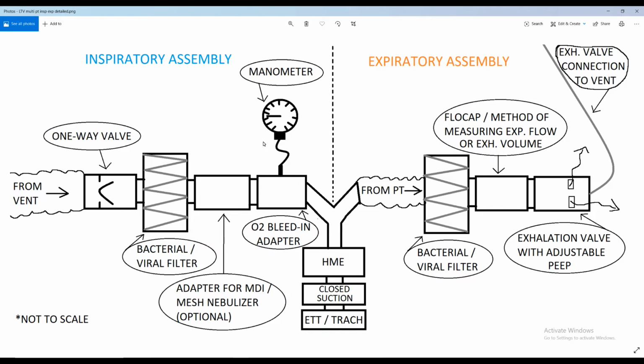So probably want to make sure our PIPs aren't going much above the 30s, 40s. So whatever your particular institution says, or whatever your physicians are comfortable allowing, we could actually figure out how much pressure is reaching the patient at their connection by adapting a manometer right here. It's the closest to the patient, it's the closest to where it would be pushed into the lungs. So that would be our most accurate, quote unquote, airway pressure measurement. This would obviously be very different than what we saw coming from the ventilator itself, where the vent's airway pressure measurement is. There would probably be a little bit of a discrepancy just because of all the runs of tubing and everything else. So when it came down to what pressures my patients are actually getting, we would want to look at this right here.